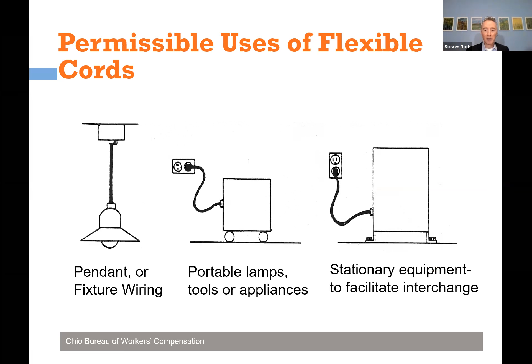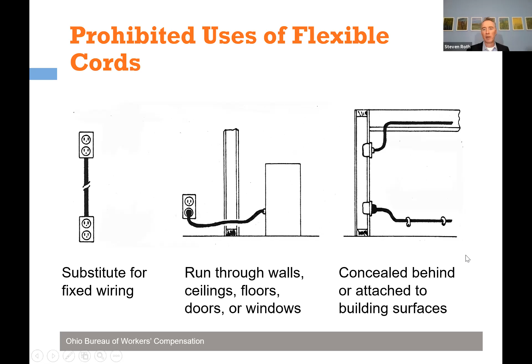Sometimes we actually use an extension cord as wiring to a fixed box, or we'll staple it or wire tie it to the building structure. This is a substitute for fixed wiring at that point, and that's not permissible. We'll run extension cords through walls, which isn't allowed because I can't see what's happening. We can't conceal it in ceiling tiles and those sort of things, because if you can't see it, you can't use it that way. Not permissible.